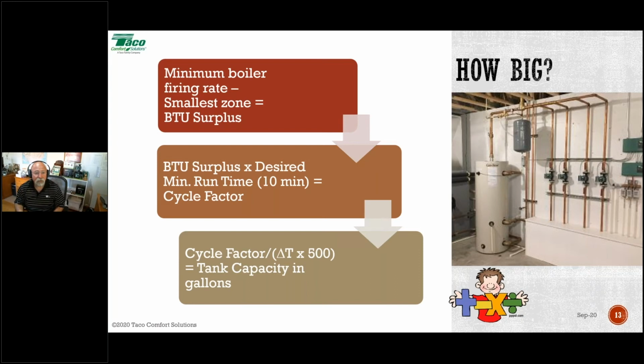The other thing that we look at is, what is the runtime that the boiler manufacturer wants as a minimum. This is what keeps that boiler from banging on and off, like we're saying, which leads it to an early grave. So we don't want that to happen. So please look and see. Most manufacturers have kind of settled on 10 minutes as minimum. But guess what? As I talked about earlier, that's absolute minimum. If you could get it to go 15, that's even better.